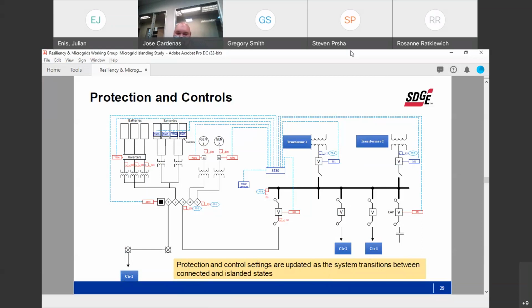Our point of common coupling for island 2 is going to be transformer number 2, and the point of common coupling for island 1 is across the 12 kV bus first breaker, which we can see with the big V right there. Island 3 is when we incorporate the 12 kV bus and that 69 kV solar plant, and the point of common coupling for that is across the tie line breaker. So we have multiple points of common coupling.